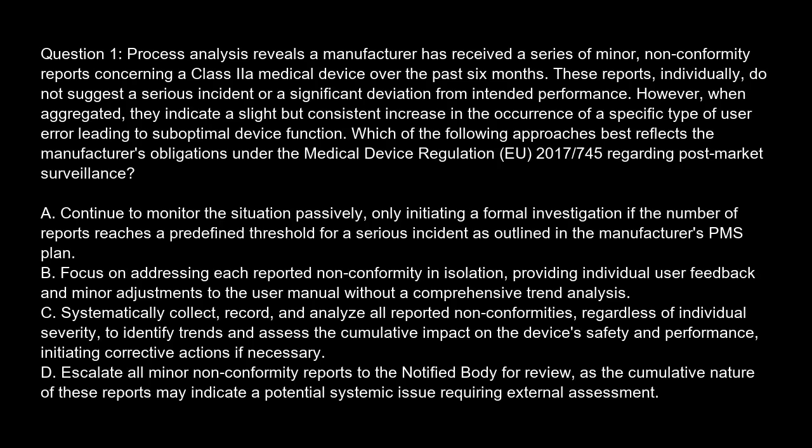Question 1. Process analysis reveals a manufacturer has received a series of minor non-conformity reports concerning a Class IIa medical device over the past 6 months. These reports, individually, do not suggest a serious incident or a significant deviation from intended performance. However, when aggregated, they indicate a slight but consistent increase in the occurrence of a specific type of user error leading to suboptimal device function.